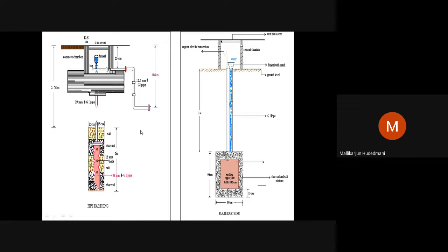In case of industry, there are hundreds of machines, with capacities of 10 kilowatt, 100 kilowatt, megawatt, like that. There could be a fault current in terms of hundreds to thousands of ampere. At that time, such a fault current has to immediately rush to the ground, be absorbed by the ground, dissipated into the ground. Then it should have a provision. That provision is done by a metallic plate mechanism. So this is how plate earthing is done in industry. Pipe earthing is done in the household.